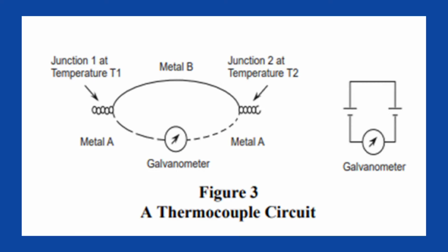If temperature T1 is higher than T2, then the voltage generated at junction 1 will be higher than at junction 2. In the above circuit, the loop current shown on the galvanometer depends on the relative magnitude of the voltage at the two junctions. In order to use the thermocouple to measure process temperature, one end of the thermocouple has to be kept in contact with the process, while the other end has to be kept at a constant temperature. The end that is in contact with the process is called the hot or measurement junction. The one that is kept at the constant temperature is called the cold or reference junction.